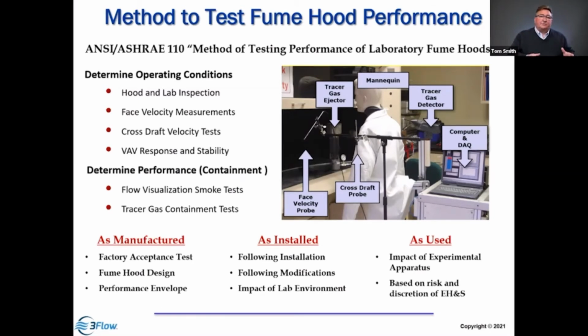Now, once we understand that the hood is properly designed, the as-installed tests are about putting the hood in the lab, installing it, and then operating the lab as it would be when the users occupied the space. We want the hood to be move-in ready when we do the as-installed, the commissioning test. Oftentimes, during construction projects, it'll get ahead of the full commissioning of the lab space or the full air balance of the systems. Just because the hood is installed doesn't mean it's ready to be tested.